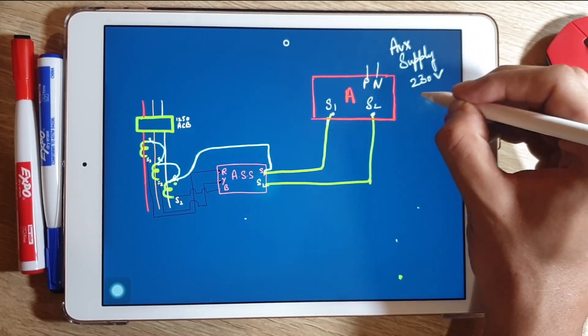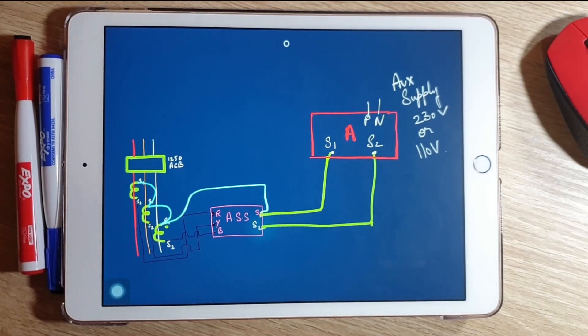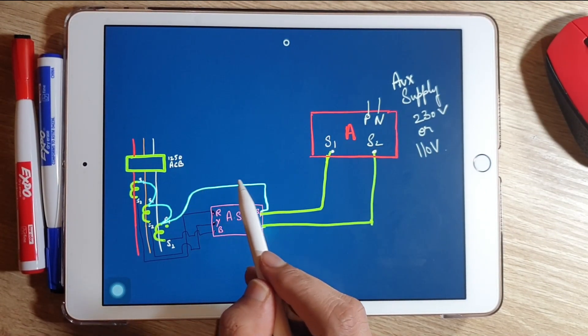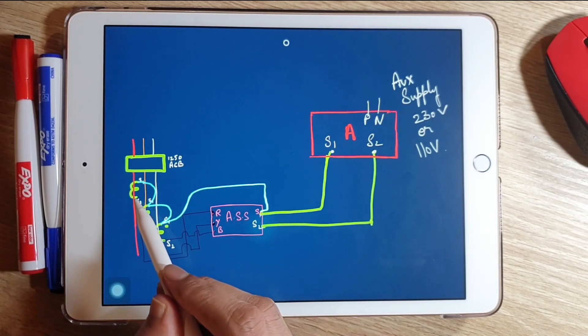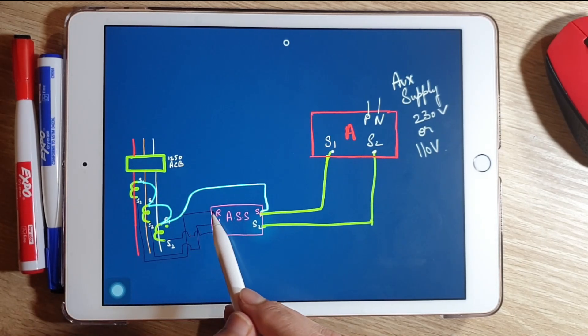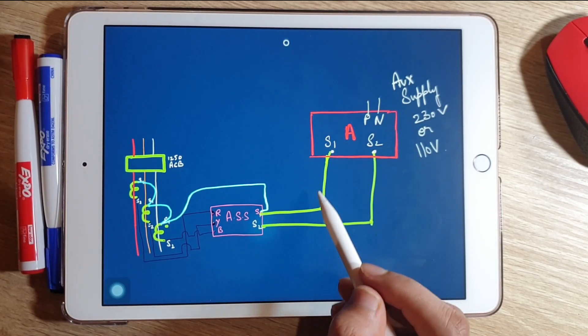Overall, the S1 terminals are looped and connected to the S1 terminal of the ammeter selector switch. The S2 terminals are connected to the respective R, Y, B phase terminals. After that, S1 and S2 from the ammeter selector switch are connected to S1 and S2 of the ammeter, and auxiliary supply is provided.